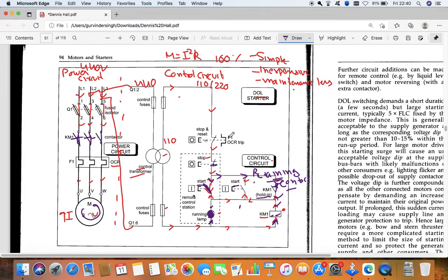Our motor also stops if your OCR relay activates, and it will open this. When the OCR trip activates, it will open up, and again your KM1 contactor de-energizes and your motor stops, without pressing the stop switch. Now here this OCR trip we need to reset. It will not come back to its original position unless we reset. When we reset, it will make contact again, and then we press the start switch, then only the supply goes from here to here. This is all about the DOL starter.